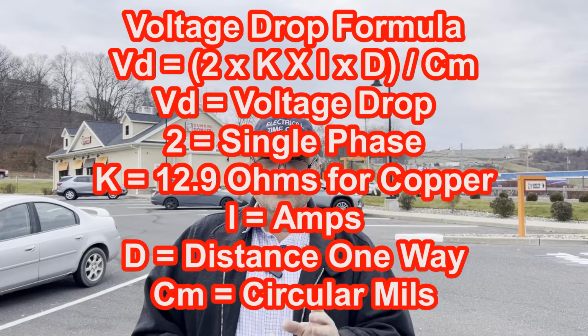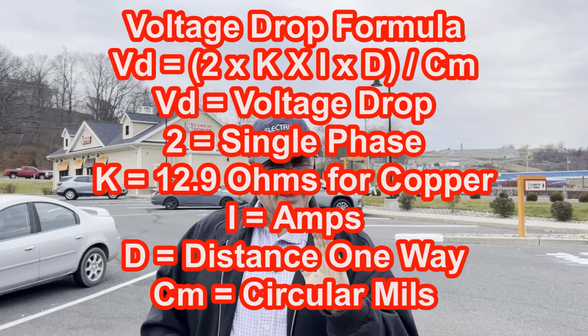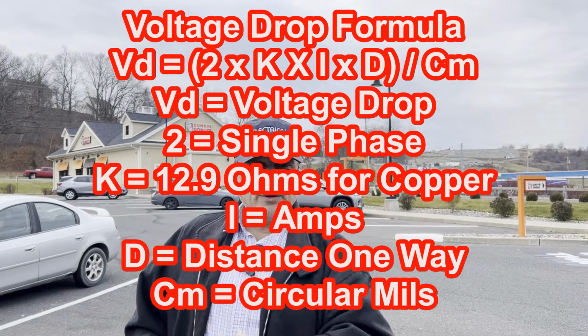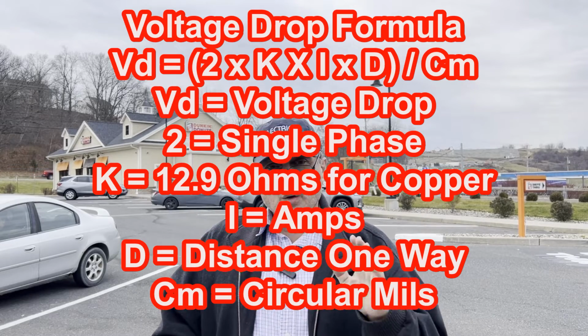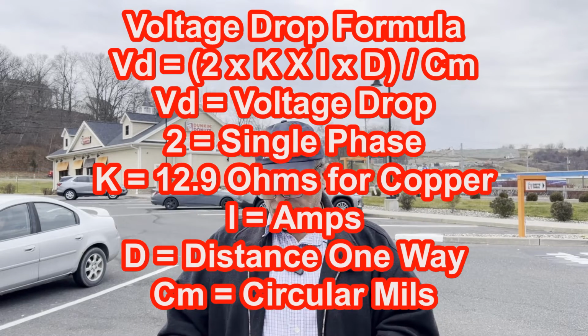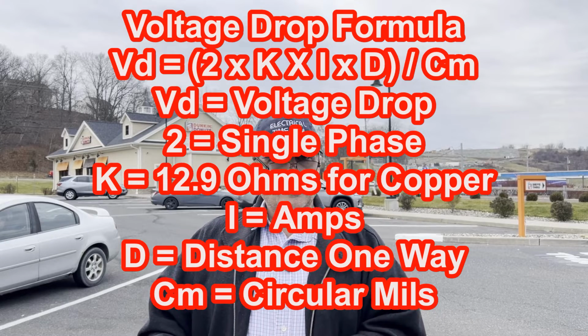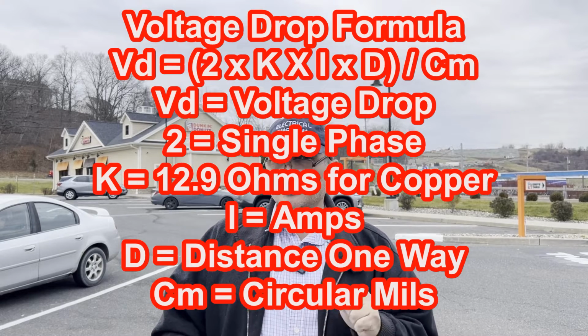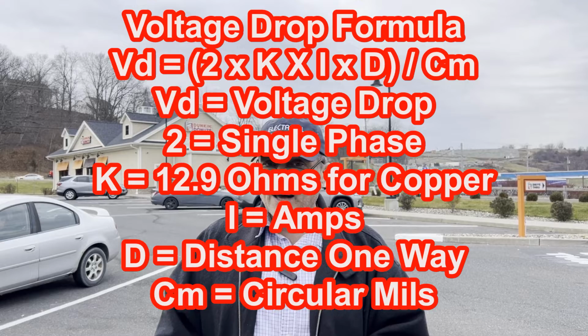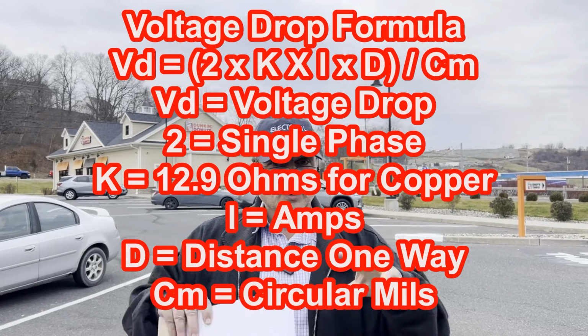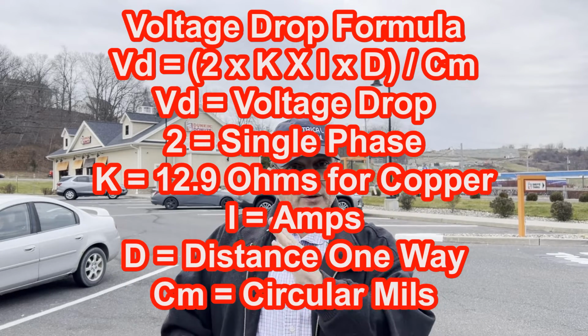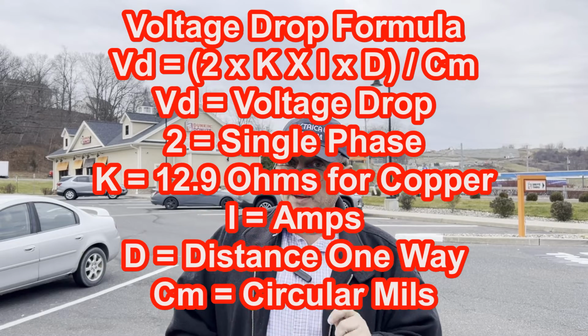So to prove that, you're now going to see on this video, we're going to do a voltage drop formula. Okay, and I'm going to say it and you're going to see it on the screen. So the long formula for voltage drop is VD, that's for voltage drop, is equal to 2 times K times I times D. You take that entire product and you divide it by the circular mils.